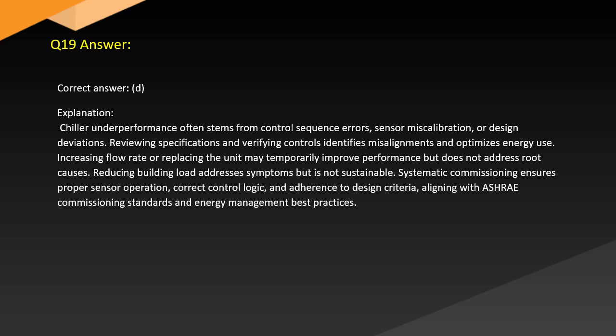Answer. Correct answer, D. Explanation. Chiller underperformance often stems from control sequence errors, sensor miscalibration, or design deviations. Reviewing specifications and verifying controls identifies misalignments and optimizes energy use. Increasing flow rate or replacing the unit may temporarily improve performance but does not address root causes. Reducing building load addresses symptoms but is not sustainable. Systematic review ensures proper sensor operation, correct control logic, and adherence to design criteria, aligning with ASHRAE commissioning standards and energy management best practices.